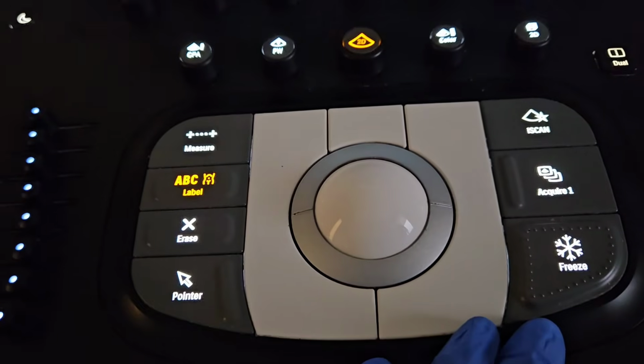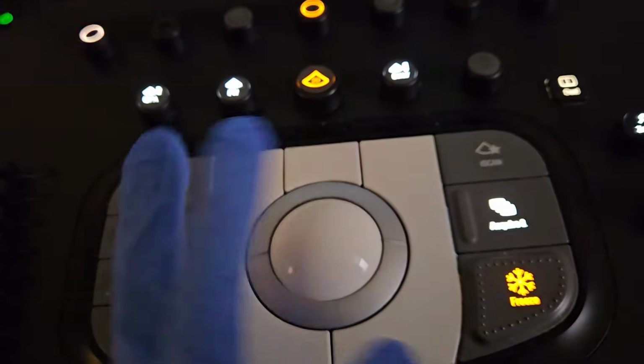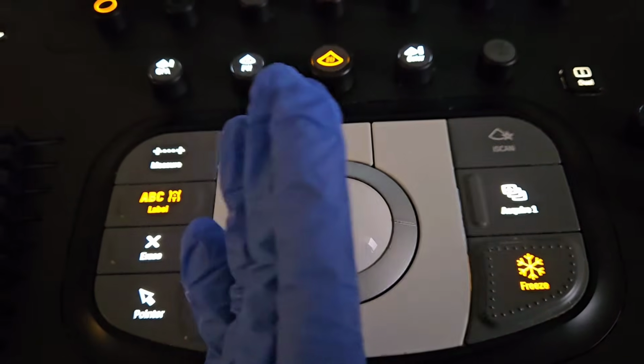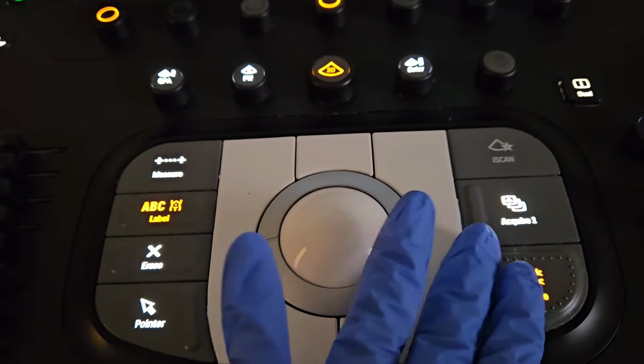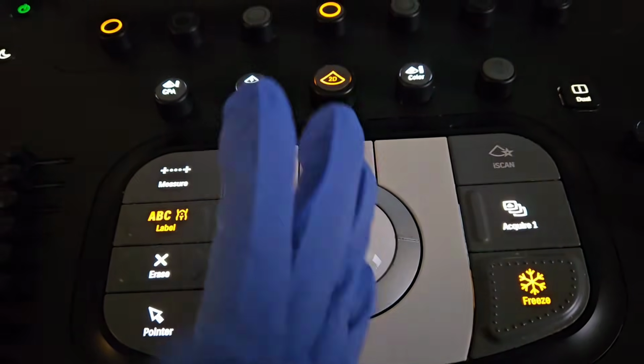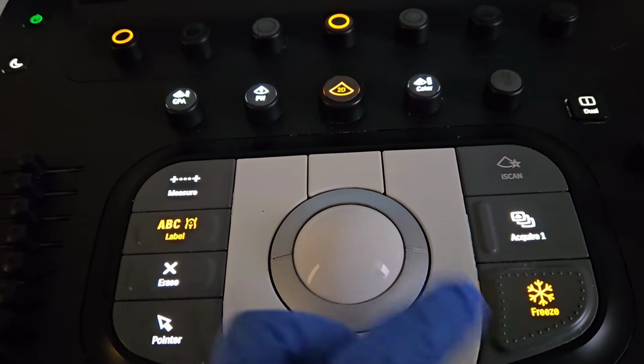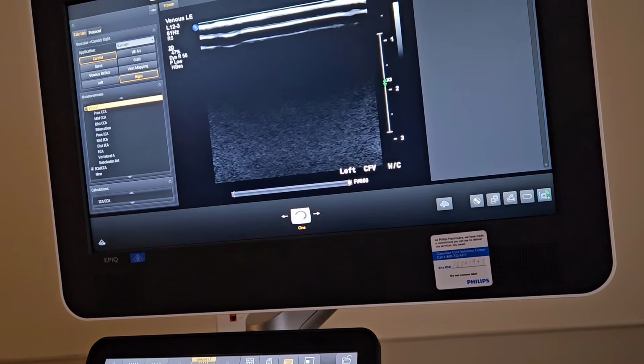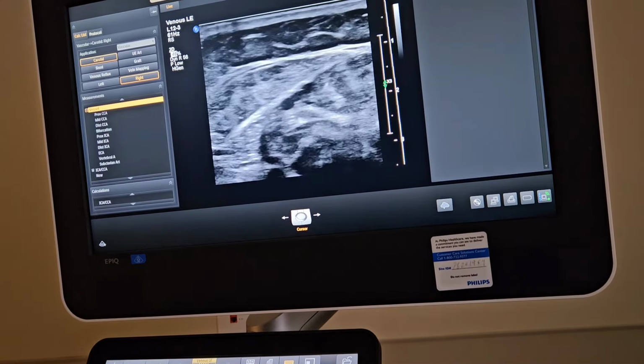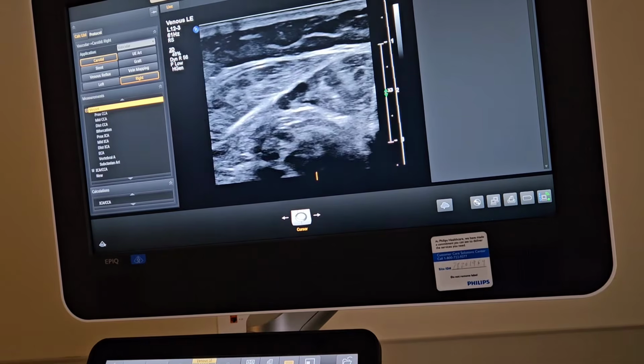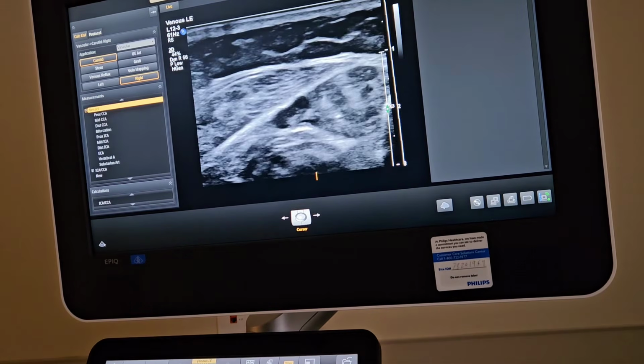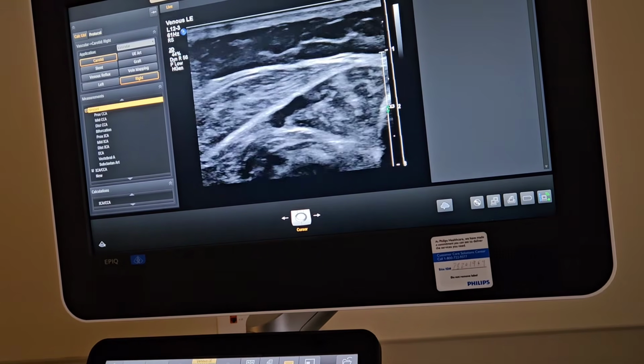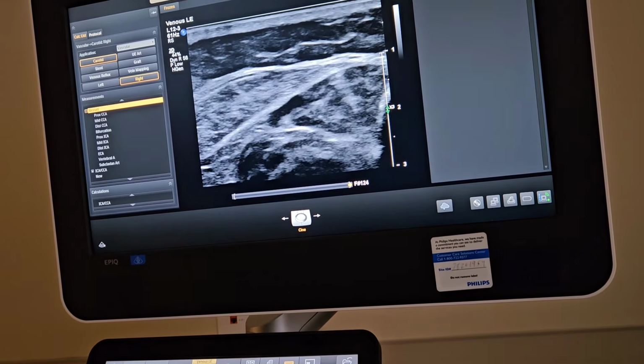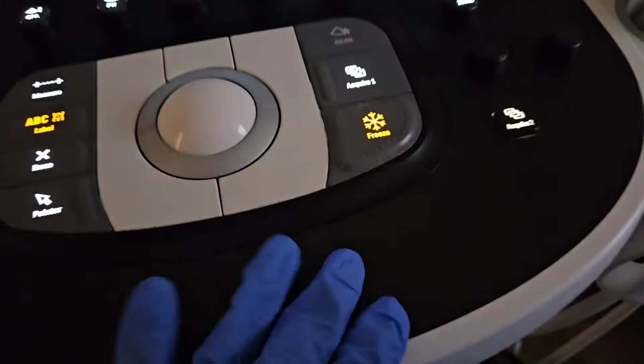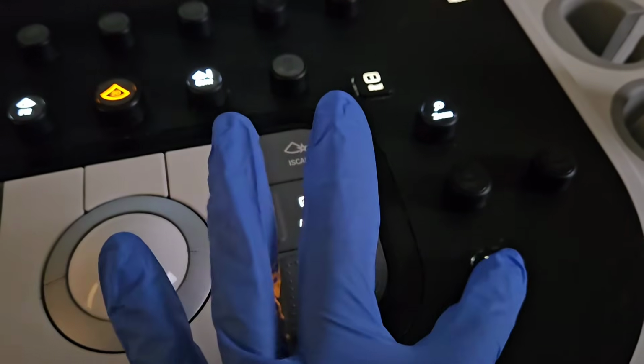Next, let's go over the freeze button. This is a very important button. Whenever you're ready to take an image, you simply hit freeze. Freezing your image does not save your image though. Once you have your image perfect, just the way you want it, you've adjusted your focus, your depth, your TGC, your gain, you hit freeze, make sure you label it, and then our next very important knob is acquire.